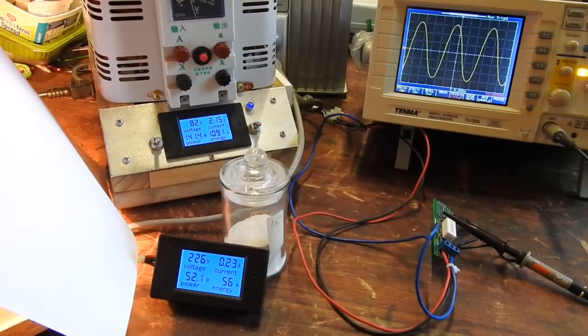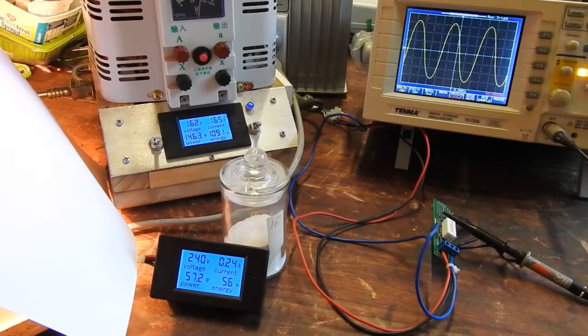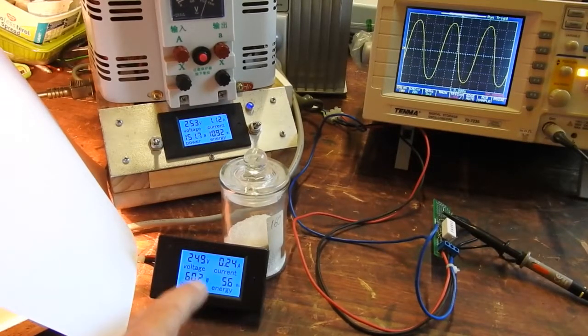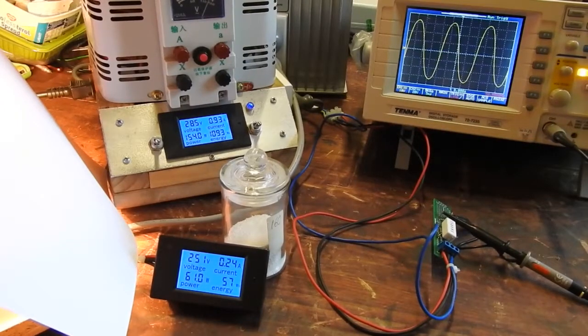As we increase it further, if you watch the waveform, it's a good sine wave now, but as the voltage goes up, you see it's starting to round out. Not really a perfect sine wave anymore, but always pretty good. 200 volts in, 245 coming out, but the waveform's distinctly rounded now, and there's typical mains, 250 volts going in, 250 volts out. Take it further all the way to 286 in, 250 out, and a rounded waveform, and that's with a 30 watt and a 25 watt bulb, so 55 watt load. Now I'm going to wind it down.